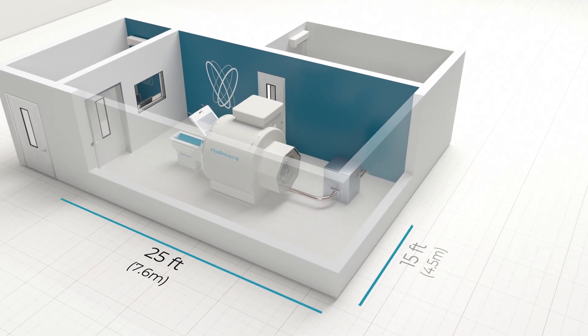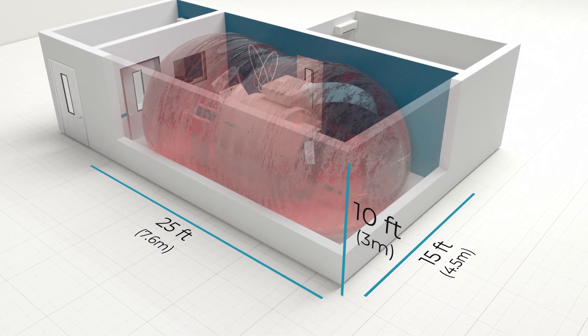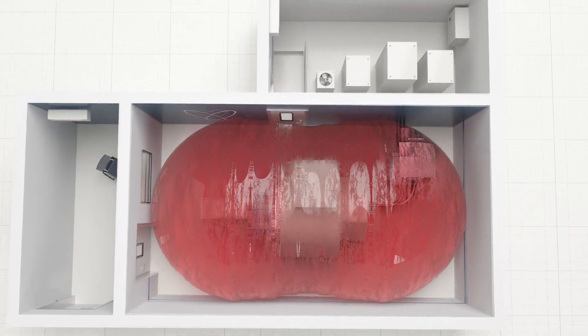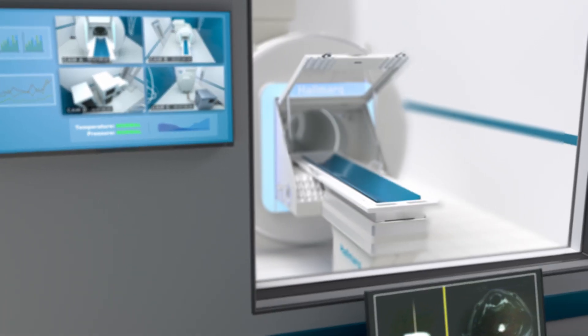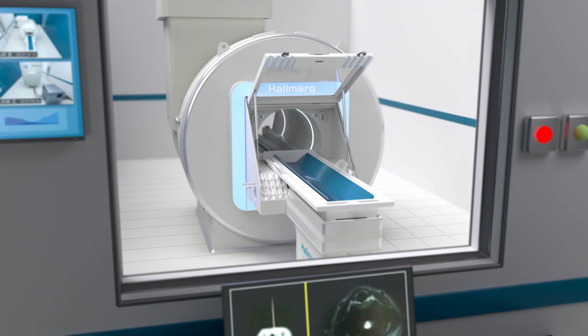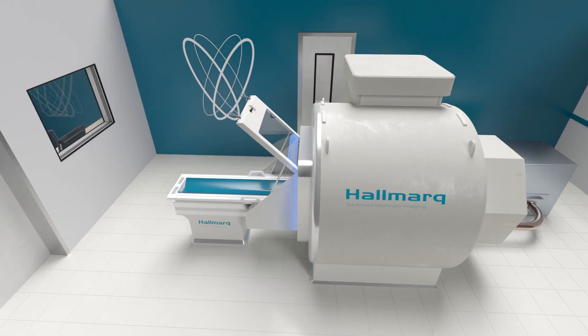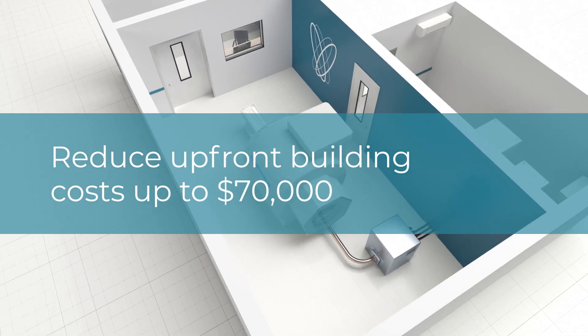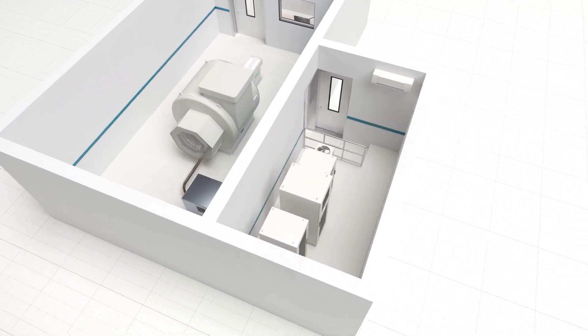Based on best practice safety guidelines, a standard in-hospital scanning room requires a space approximately 25 feet long by 15 feet wide and at least 10 feet tall — large enough to encompass the five gauss magnetic field. But unlike human-specific MRIs with complex and expensive radio frequency shielded rooms, the scanning room for a Hallmarq small animal MRI can be constructed using conventional building methods and materials, ultimately reducing upfront building costs by as much as $70,000.